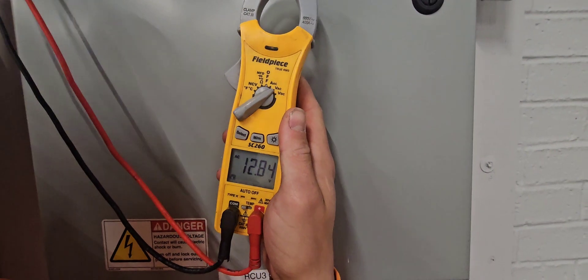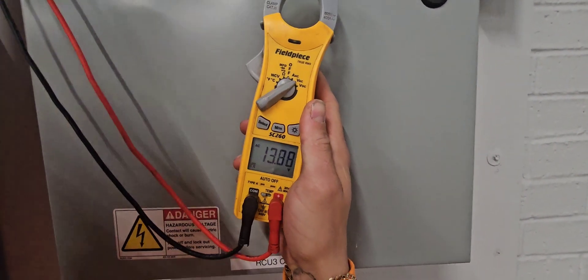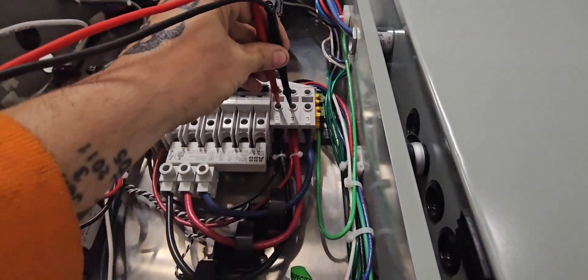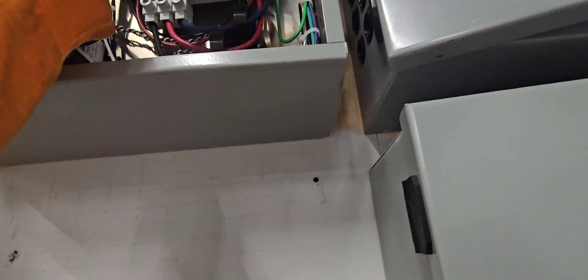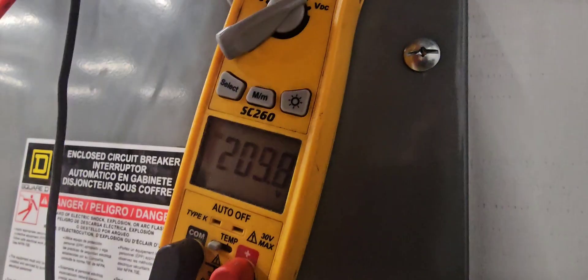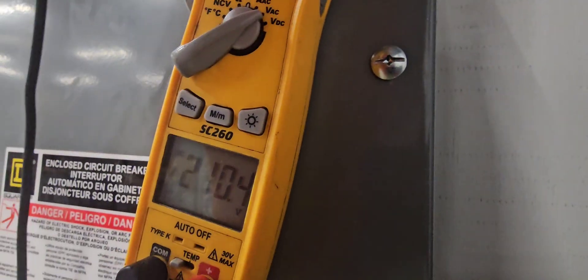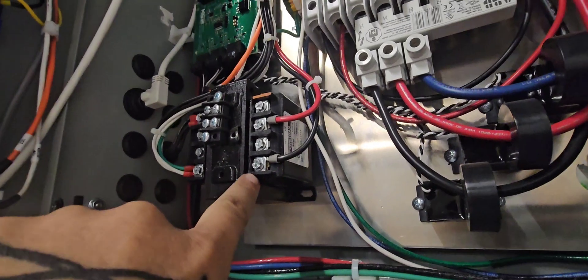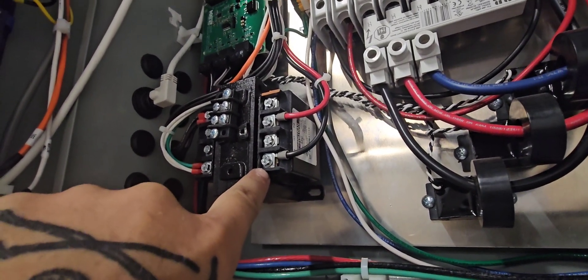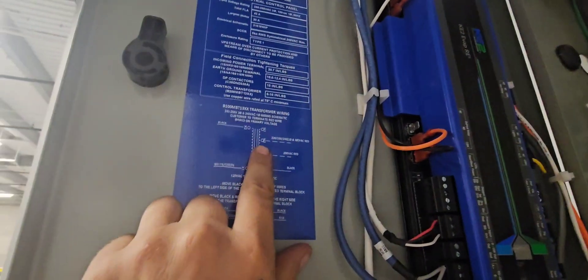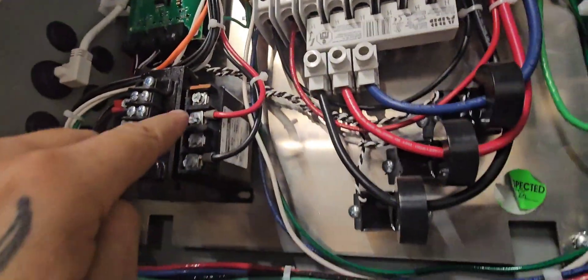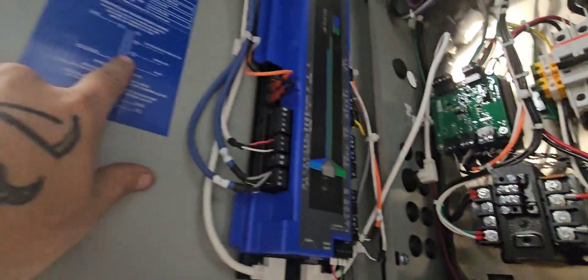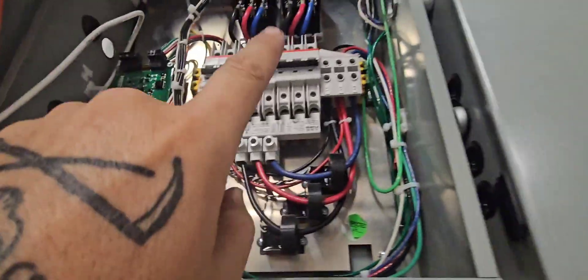So same thing just checking across L1 L2, got 210, 1 and 3, and then 2 and 3. So 208. And what I've been noticing with all of these, transformers are all tapped wrong. So that's set up for the 230 side. So before we turn these on I'm actually going to switch these transformers over so that way they're tapped on the 208 side. We'll do that and then we'll hit that breaker.